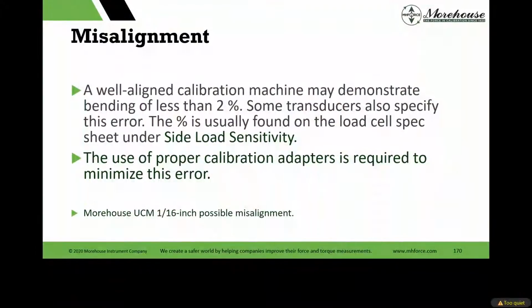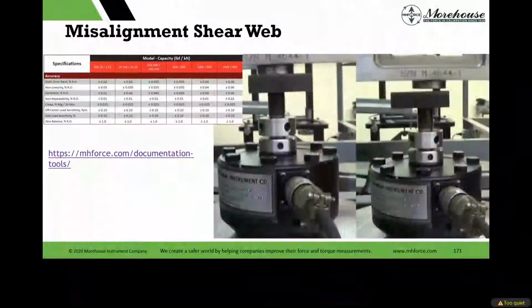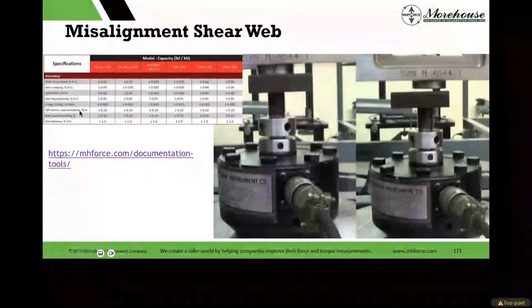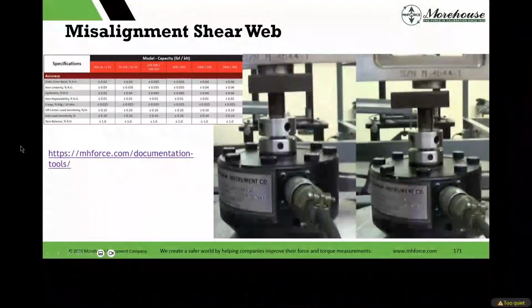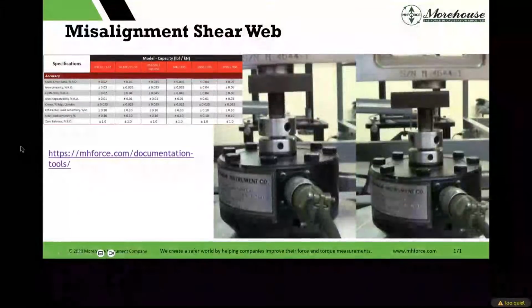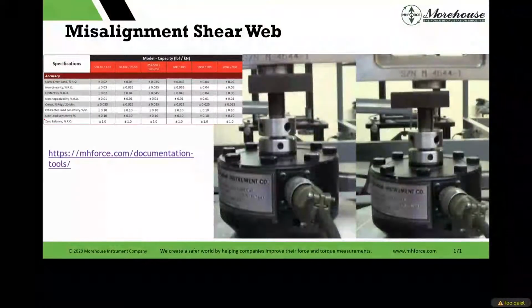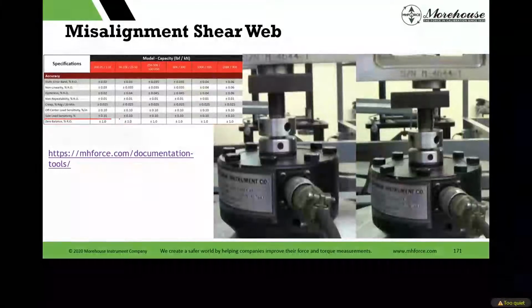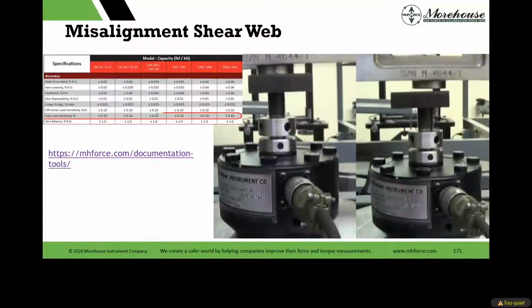Misalignment: most of our machines demonstrate bending of less than 2%. Also specify this error. The use of proper cal is required to minimize this error, and you keep going on and on. There's that picture. Here's the spec sheet. What we're looking at is that side load sensitivity. I had pulled that out when we were showing the uncertainty, but you look at this number here when you put it in a cal machine, and those other documents made reference to that.